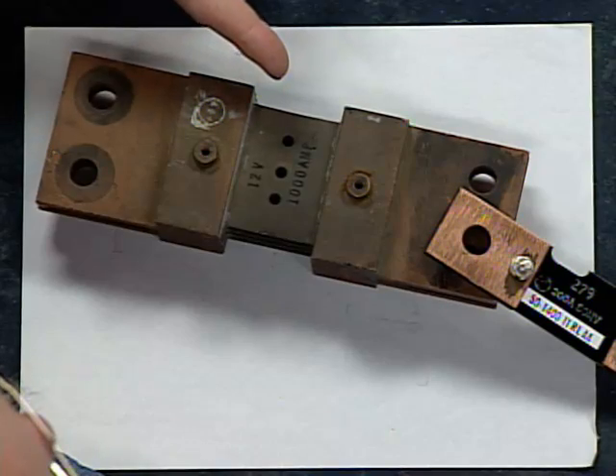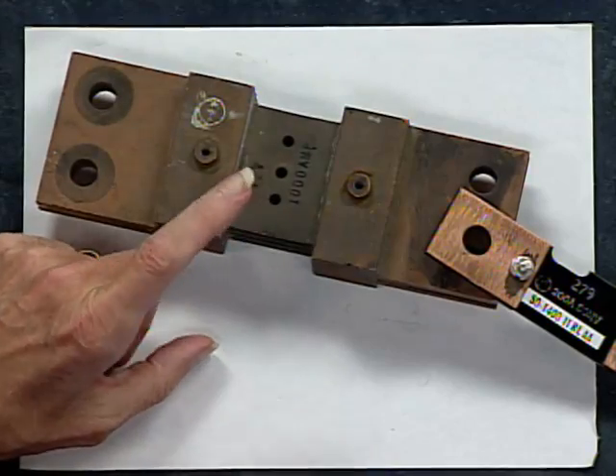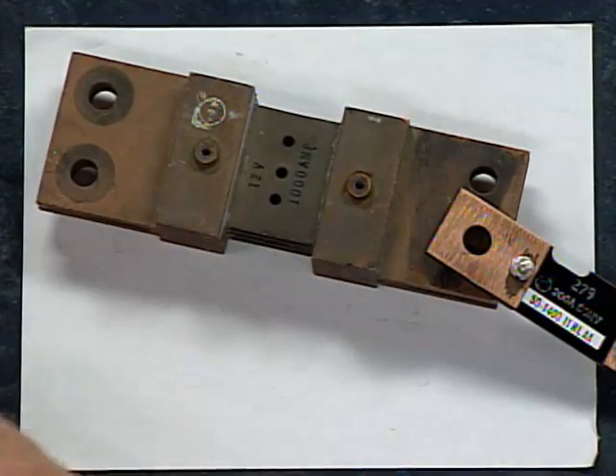You could put that in series with a 1,000 amp, 120 volt circuit, but I don't know who would have that, and that's not a good idea. I think this is rated for 12, that's the voltage rating, a circuit voltage rating, and I wouldn't want to get pushy about it. So you put one of these in series with one of these, and we can say, let's calibrate these guys.